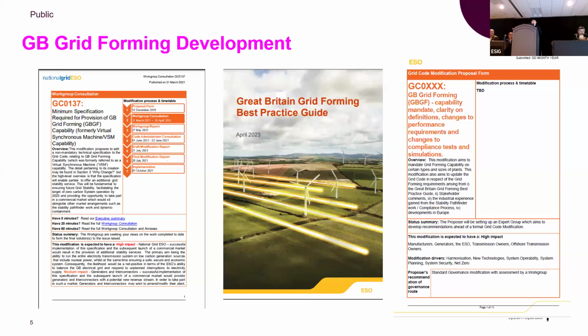Around 2022, we developed a grid forming specification within the grid code. That's GC0137, which got approved by the system regulator. I have to say this specification is non-mandatory. It means that if a generator wants to behave like grid forming, this is the technical specification for that, but it's not mandatory. You don't have to behave like grid forming. You can still operate like grid following.